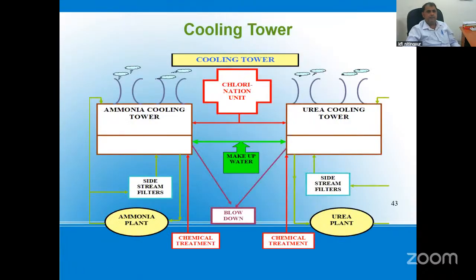This is the cooling tower circuit: ammonia cooling tower, urea cooling tower. Since our requirement is huge, we have 12 cells of cooling tower. Our requirement is about 40,000 meter cube per hour. Such a huge quantity cannot be cooled by a single tower, because a very wide diameter of fan would be required. So we divided the towers into 12 sections. Some are used for ammonia and some are used for urea.